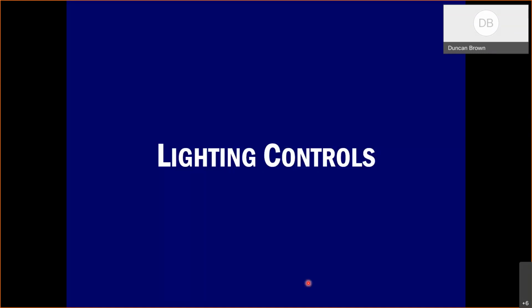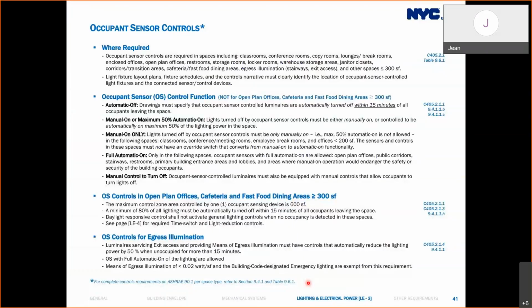So lighting controls, they are pretty extensive and complicated requirements in commercial buildings. So today we'll take a look at just a few pages in the how-to guide and check one of the email inquiries we received through the Energy Code technical email account. On page 3 of the lighting and electric power section, LE3, we summarized occupant sensor controls, where occupant sensors must be provided and how they must function to automatically turn on and off the lighting depending on the area and use types. And we have a separate section for the open plan offices, cafeteria, and fast food dining areas of 300 square feet or greater, and another separate controls section for egress illumination.